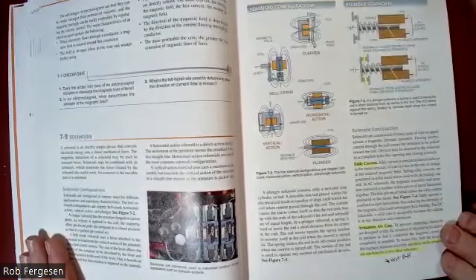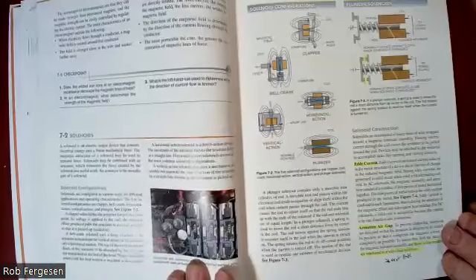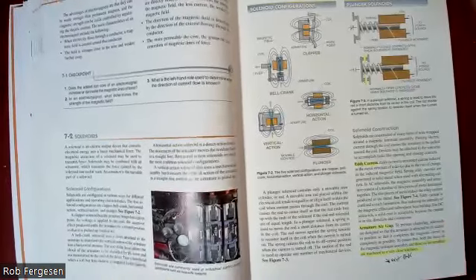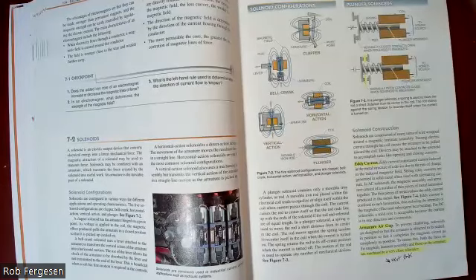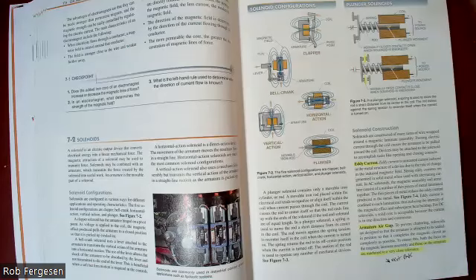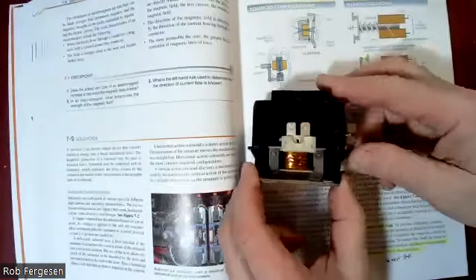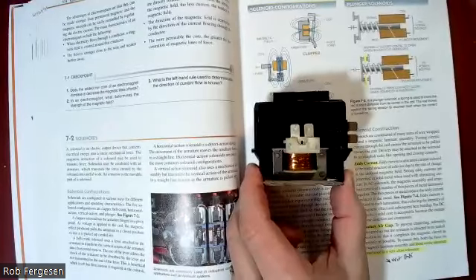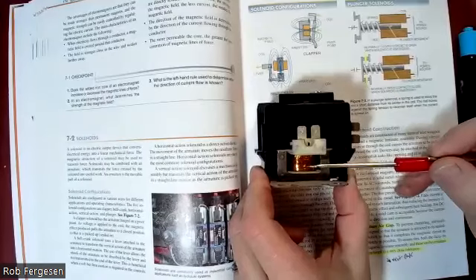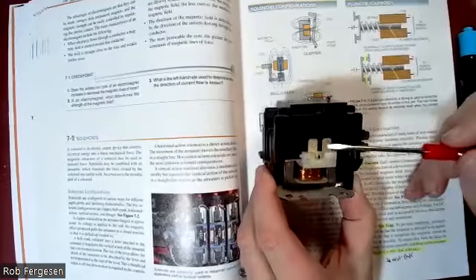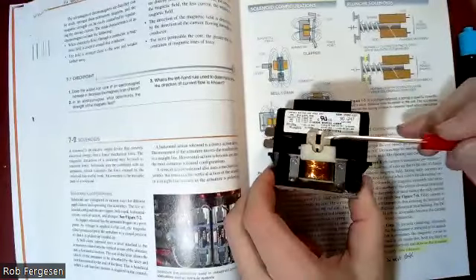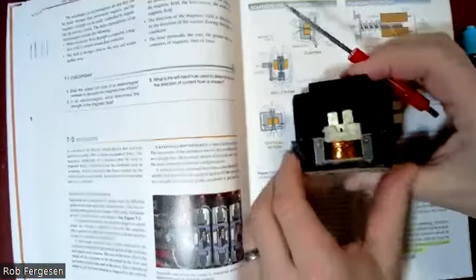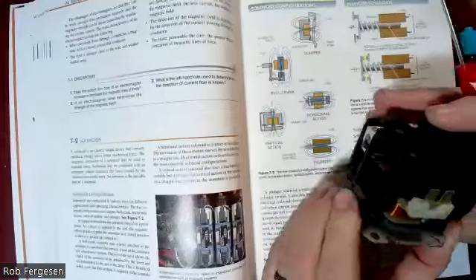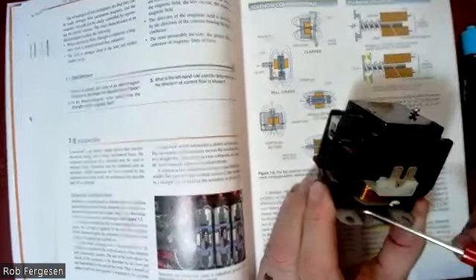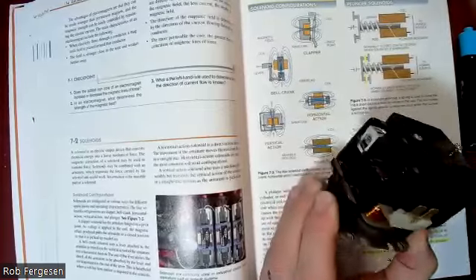In 7.2, we talk about solenoids in general, and it talks about the various solenoid configurations out there. There's a lot of different kinds of solenoids because you can position a magnet that sucks in a contact in a lot of different configurations. For instance, right here, we have the contactor that I mentioned, and down at the base, you've got your coil. There's your little coil of copper wire. That little coil, one end is attached to this tab, and the other end is attached to the tab on the opposite side. And so when I energize this coil, this entire metal frame down here gets turned into a magnet, and it sucks down.